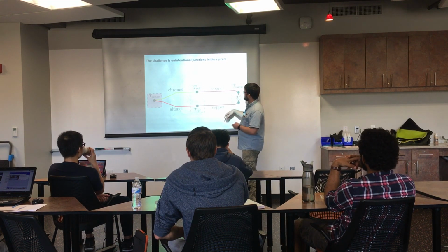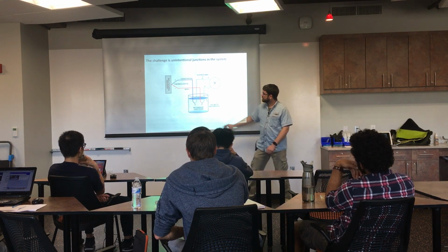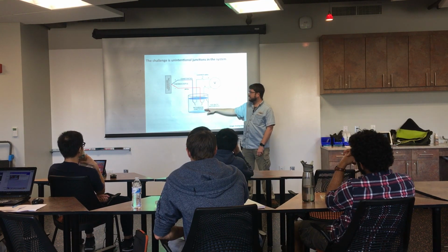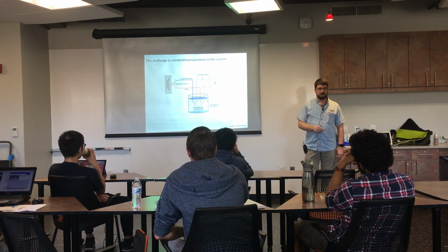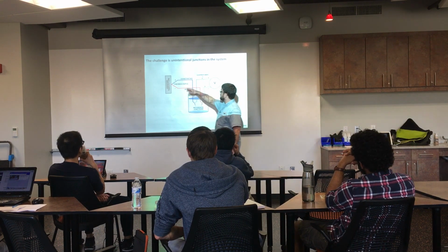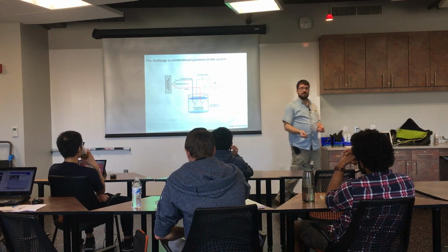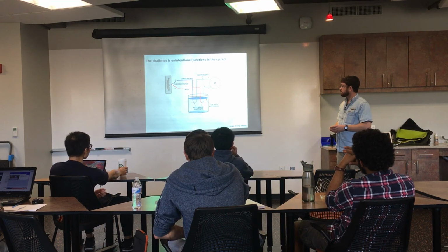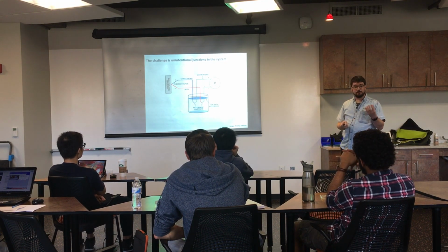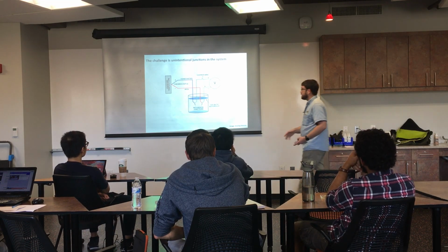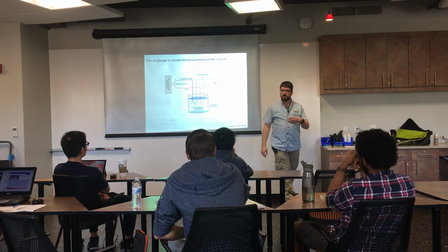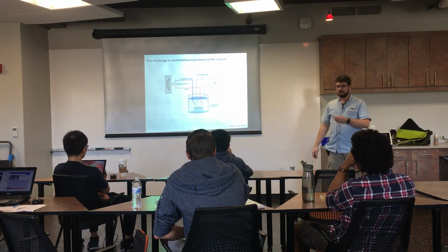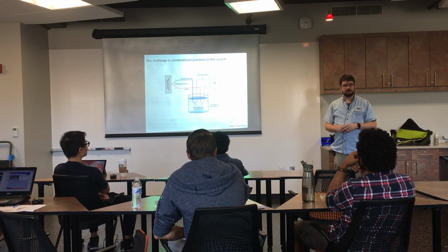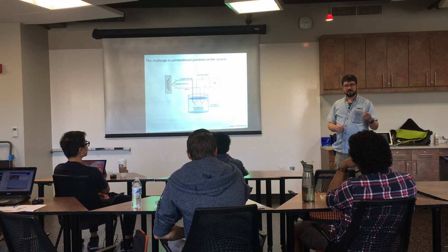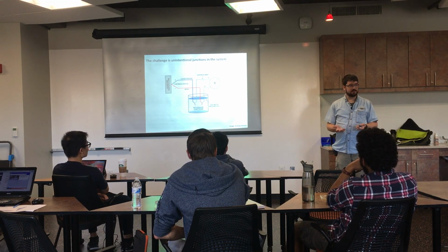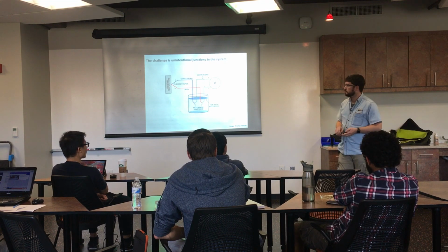When they calibrate these, they actually put those junctions, they're called the reference junctions, in a bath of ice water, so we know they're exactly at 0 degrees Celsius, and then calibrate the thermocouple, and that's where we get these standard tables of how many millivolts out per a certain temperature. Then now in software, if we measure the temperature of the room that we're doing this in, we can correct for those. It's called a cold junction correction, cold junction compensation. This is a really bad source of error for people when they don't correct for that, because then the temperature that you think you're measuring is a combination of your experiment and the room temperature, which in this building is a very bad thing, because our building temperature varies all over the place.